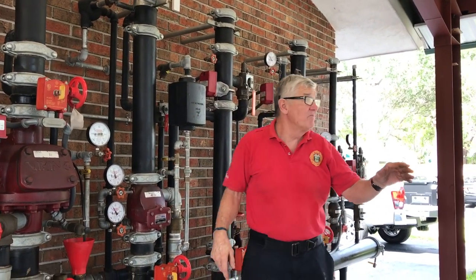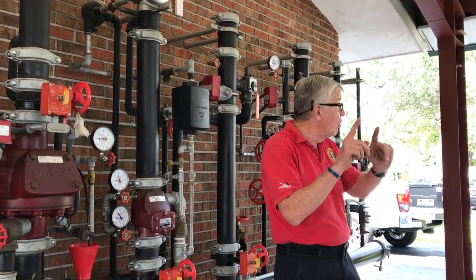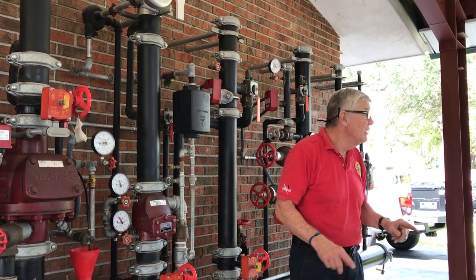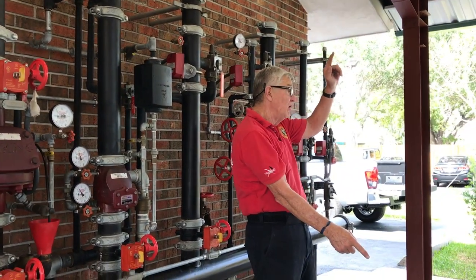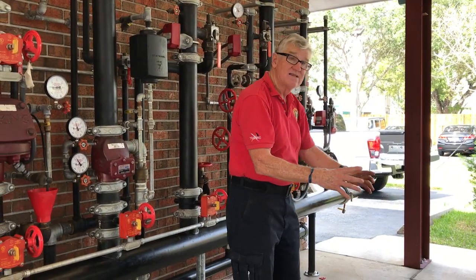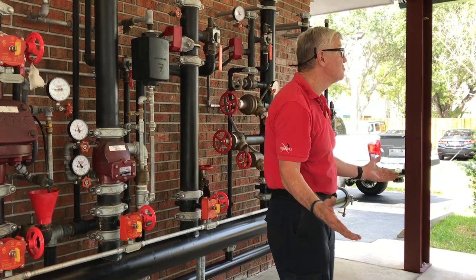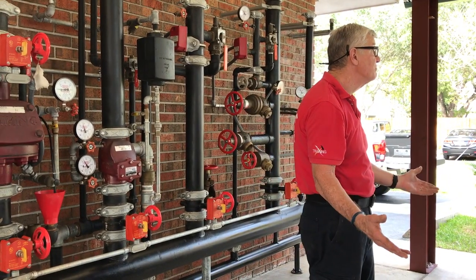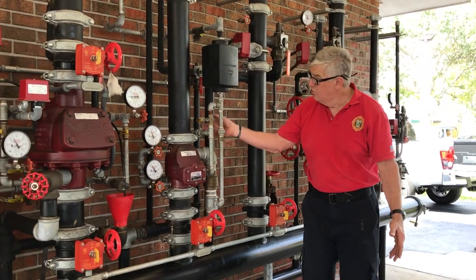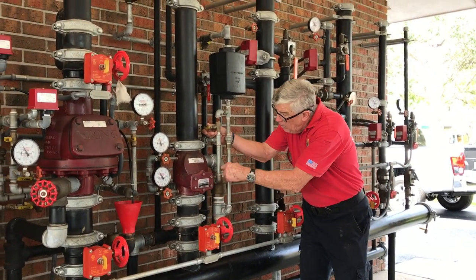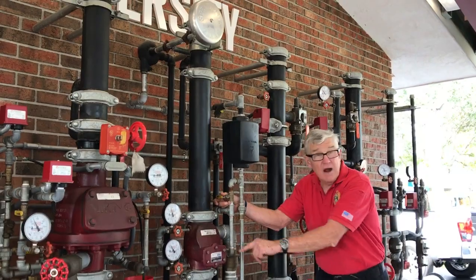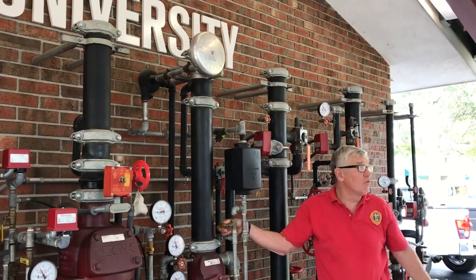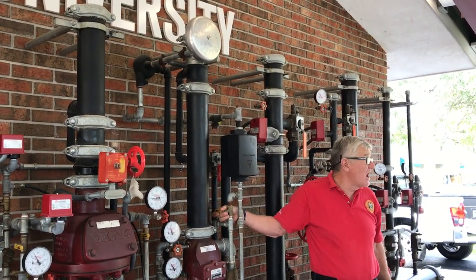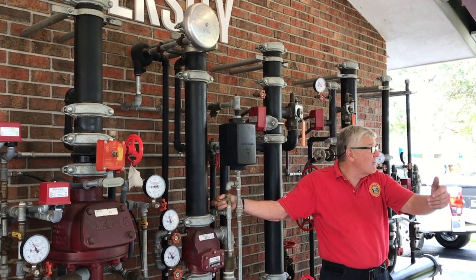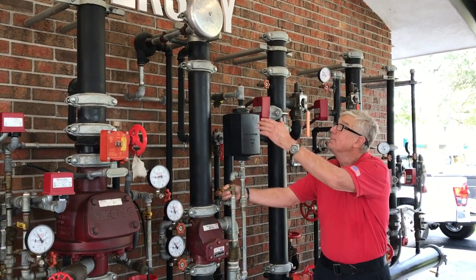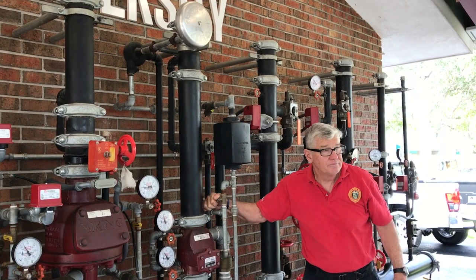And I'll tell you this, if you have a building that has the old school water motor gong, you'll see a drain at the base of the bell. If there's a puddle of water and it's not still flowing, it was a pressure surge. It was a surge in the system. So I'm gonna move this lever and allow water to bypass the alarm check valve. We're gonna fill the retard chamber. Once the retard chamber is filled, fills faster than it can empty, we will ring the water motor gong.